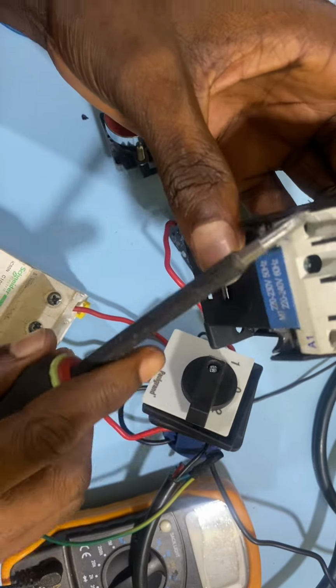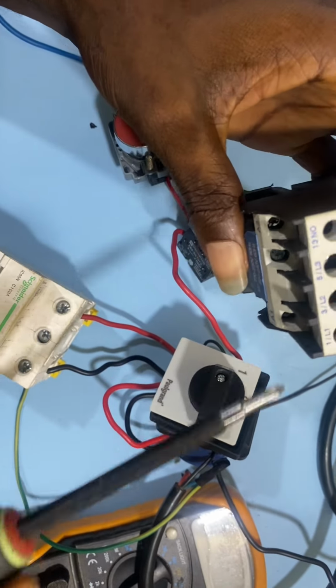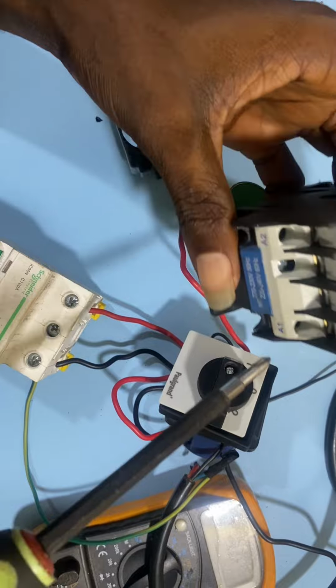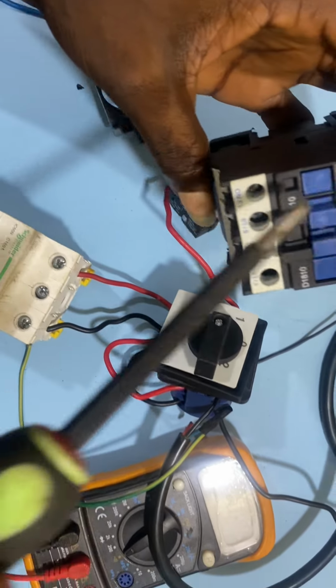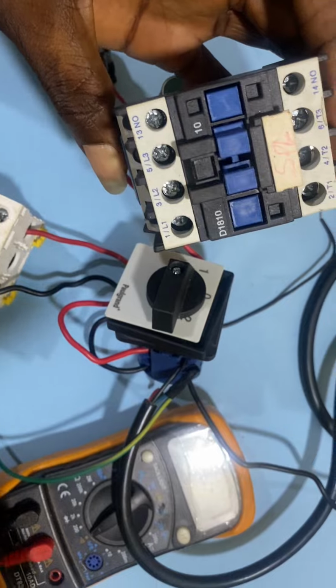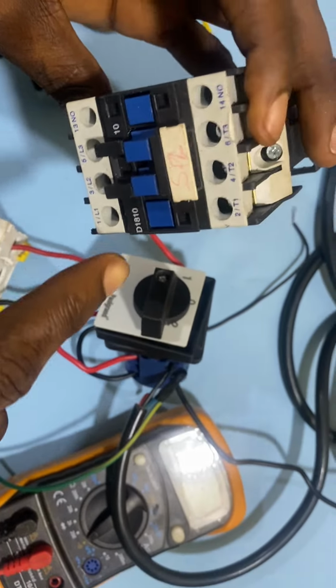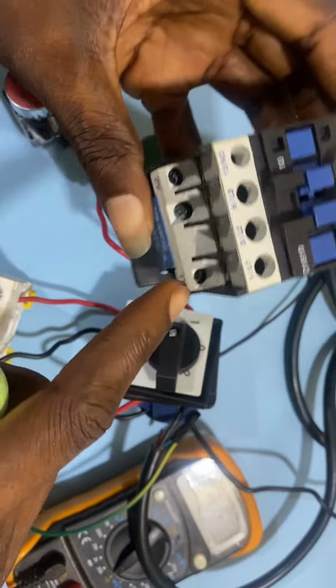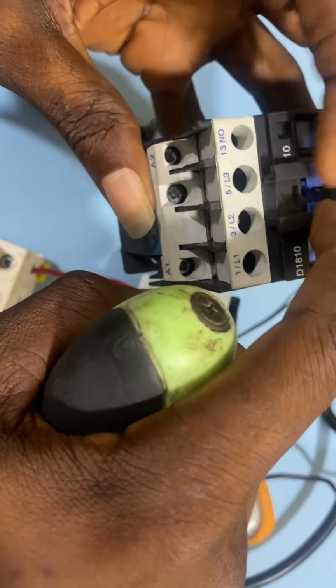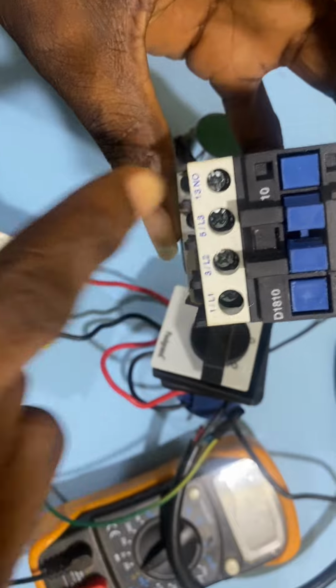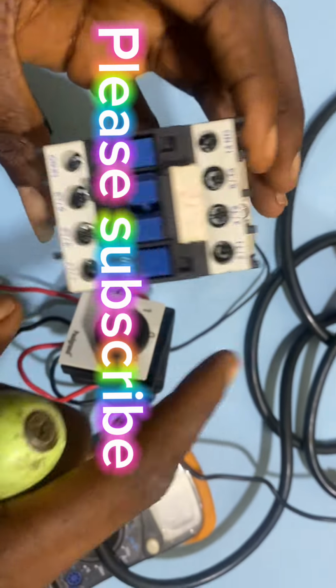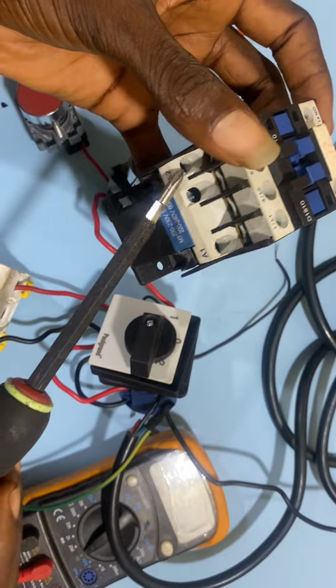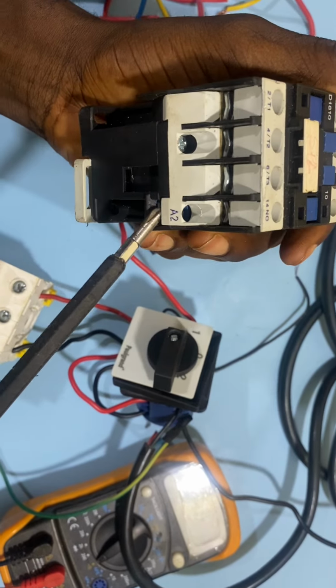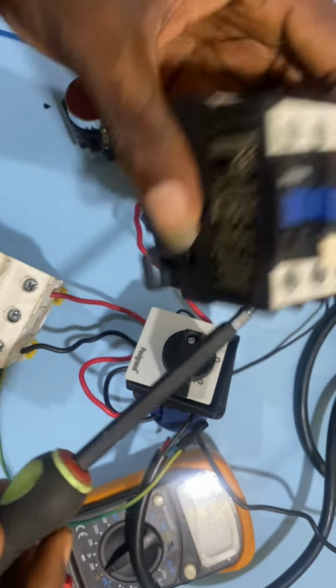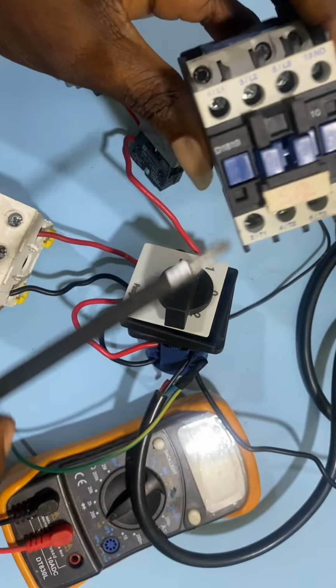So what I'm going to do is to connect this, the coil contact of the contactor, which is the A1 and the A2. So you know that when the coil contact of the contactor is energized, the normally open contact of the contactor will turn normally closed, and the normally closed contact will turn normally open. And you notice that as soon as the coil contact of the contactor is energized, this knob will drop down to allow the easy flow of current from the normally open contact, that is here to here. And this contact has a neutral terminal at this point, connected also to a neutral terminal at this other side. So if you connect the neutral here or you connect it here, it's still going to work the same. So I want to connect mine here.